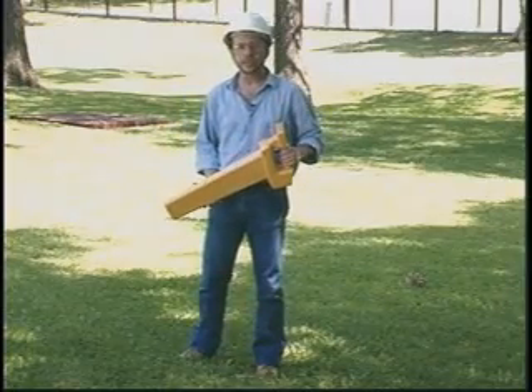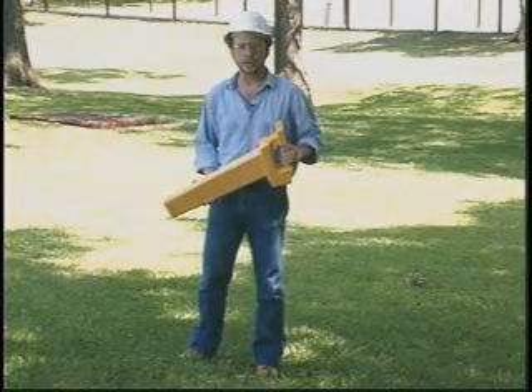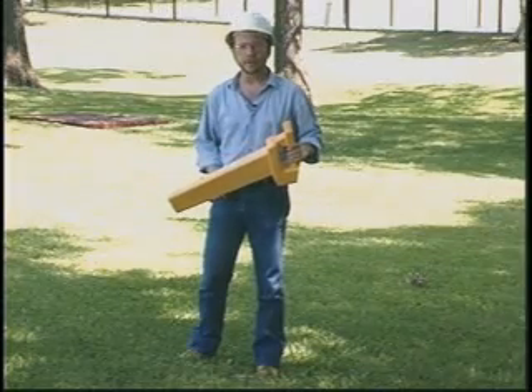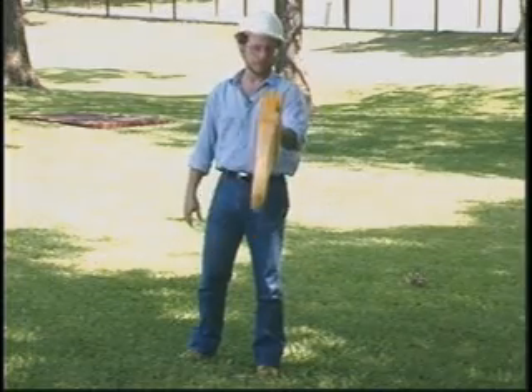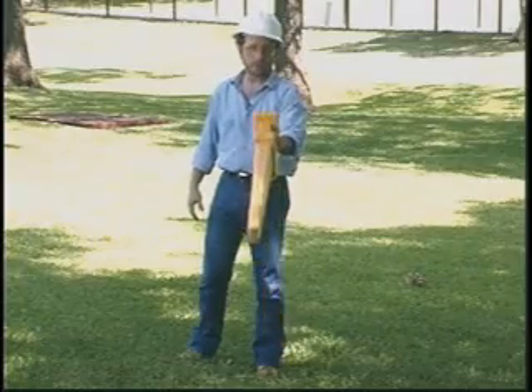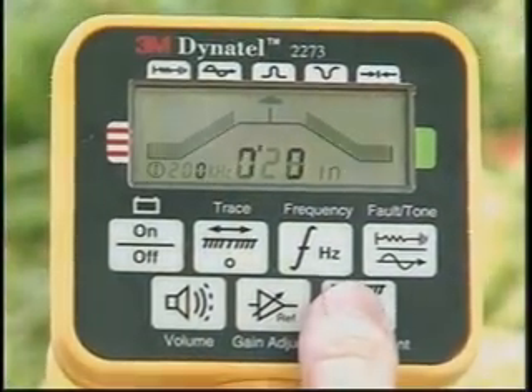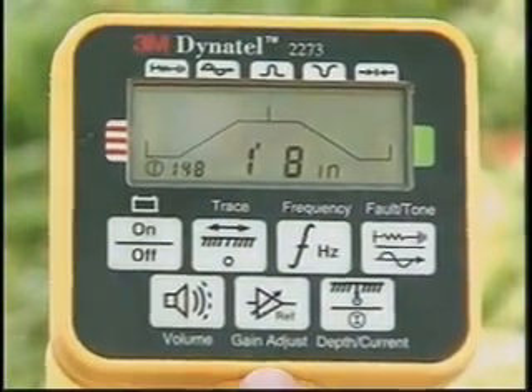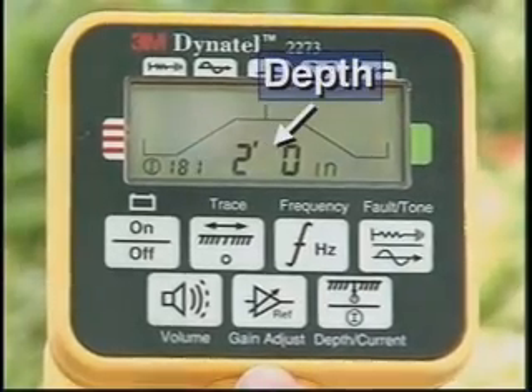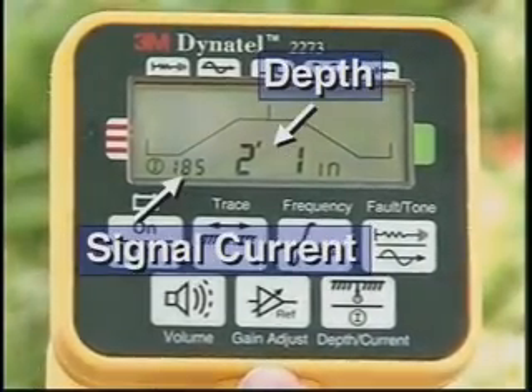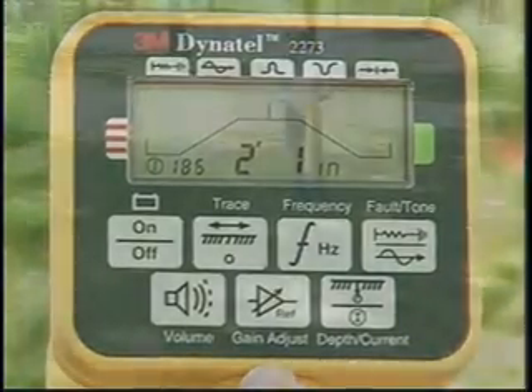At any time while tracing, you can get an estimate of the cable's depth. Set the receiver on the ground directly above the cable, with the receiver's handle in line with the cable path. When you press the depth key, the numeric display shows the estimated depth and the relative signal current in the cable. The circled I is also displayed.